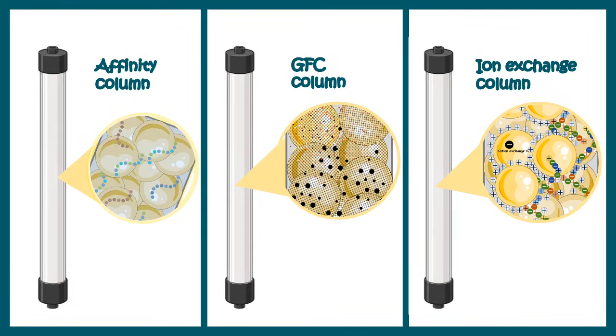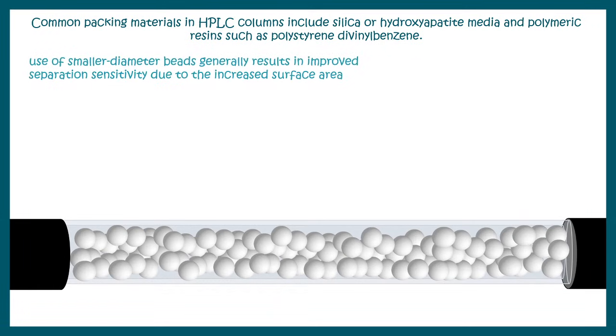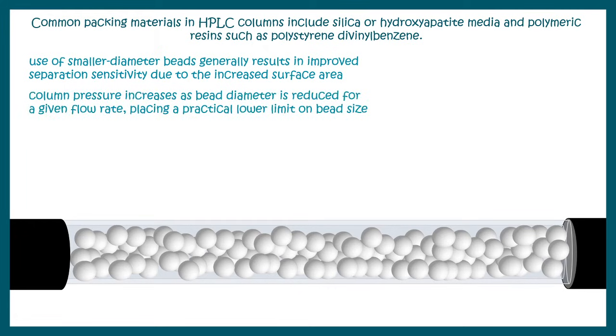The HPLC column materials include silica, hydroxyapatite media, or polystyrene-type beads that can withstand very high pressure. Usage of smaller diameter beads generally results in improved separation due to the increased surface area. However, column pressure increases as the bead diameter is reduced, so there is always a cutoff limit on how small the bead size can go.